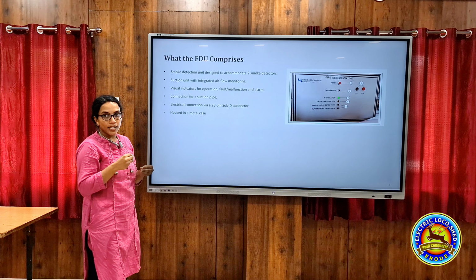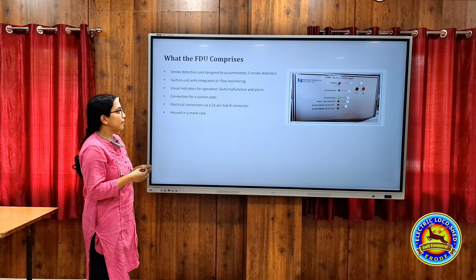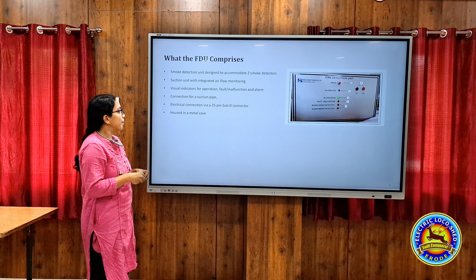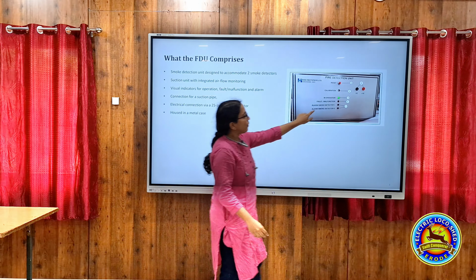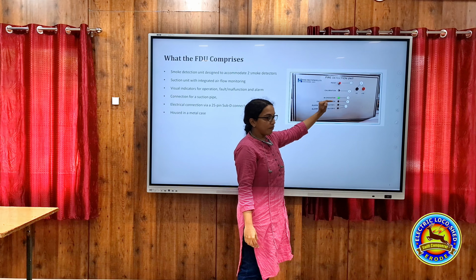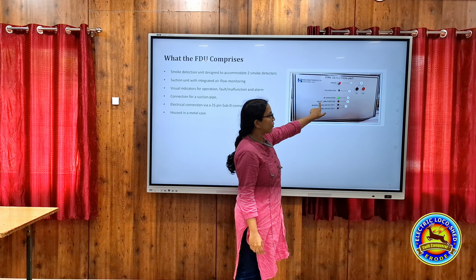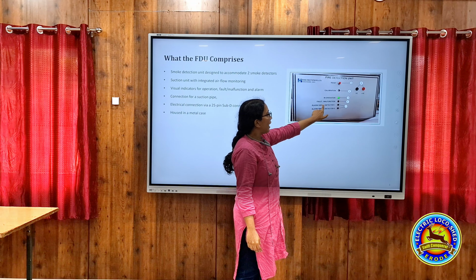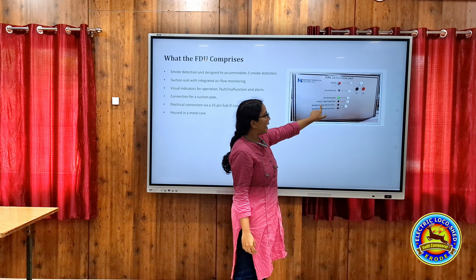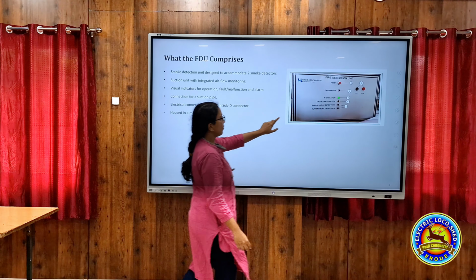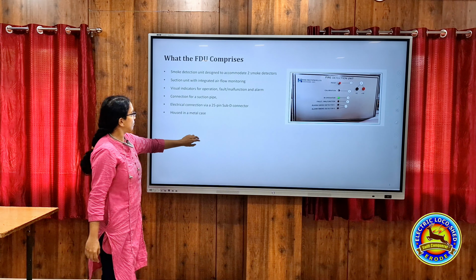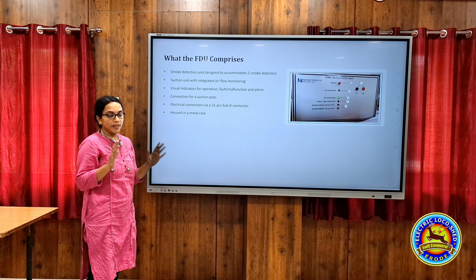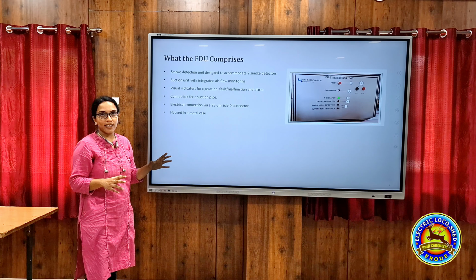For electrical connection, we are using a 25 pin sub D, and there are visual indicators for fault and malfunction. This one glows when the FDU is in operation, and this one is for fault malfunction indication. And there are two alarms, 1 and 2. The whole thing is housed in a metal case.